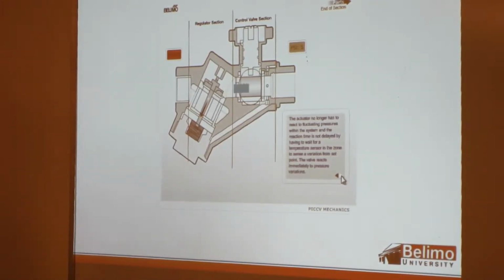As long as you're in that 5 to 50 psi drop across the valve, you won't see any changes in the flow through the valve based on just pressure changes. You're only going to see changes if the building automation system calls for a change in opening.